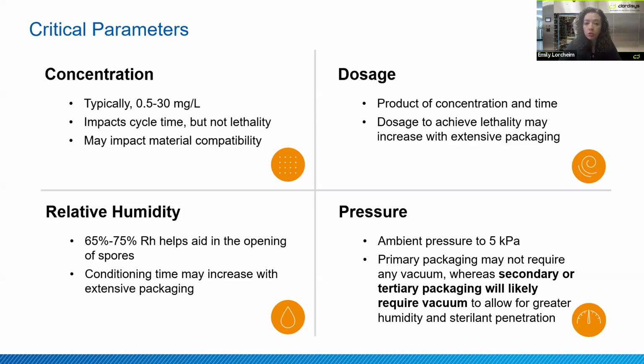Dosage is the product of concentration and time. So just as I mentioned, it's going to be concentration and time. That gives you your dosage, and dosage is what you would validate because you can have a consistent one as long as you fluctuate those other parameters. That dosage is what's going to indicate lethality. Relative humidity, as I mentioned, helps aid in spores opening up and allowing the sterilant to penetrate. And the key thing, though, is that relative humidity in the conditioning time may need to increase with added packaging. So when you want to send your product to be validated, we'll evaluate your packaging selection in determining what kind of conditioning time is necessary, as well as what relative humidity is proper.